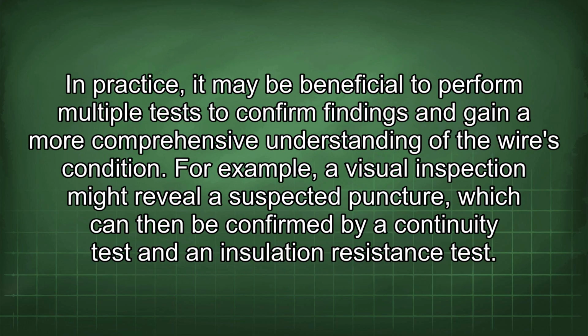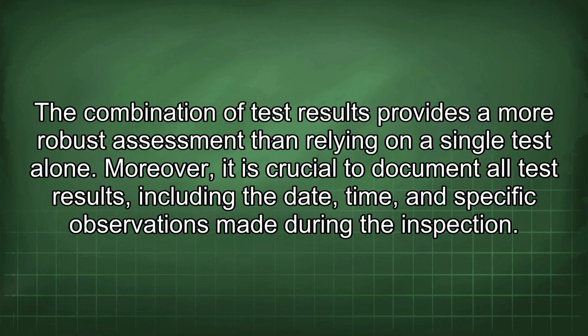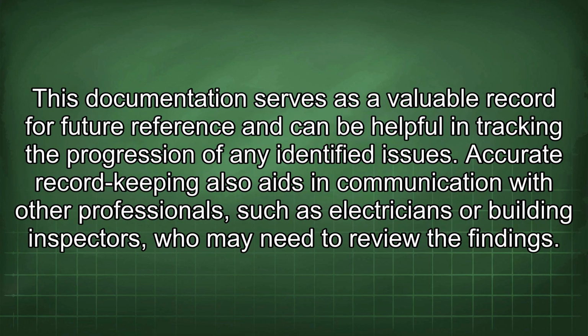In practice, it may be beneficial to perform multiple tests to confirm findings and gain a more comprehensive understanding of the wire's condition. For example, a visual inspection might reveal a suspected puncture, which can then be confirmed by a continuity test and an insulation resistance test. The combination of test results provides a more robust assessment than relying on a single test alone. Moreover, it is crucial to document all test results, including the date, time, and specific observations made during the inspection. This documentation serves as a valuable record for future reference and can be helpful in tracking the progression of any identified issues. Accurate record keeping also aids in communication with other professionals, such as electricians or building inspectors, who may need to review the findings.